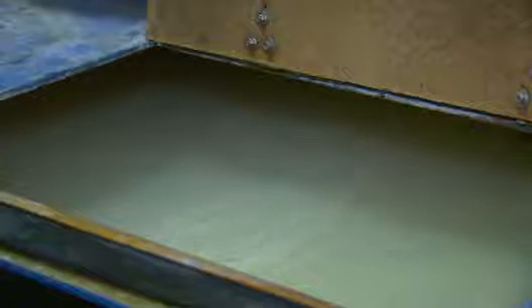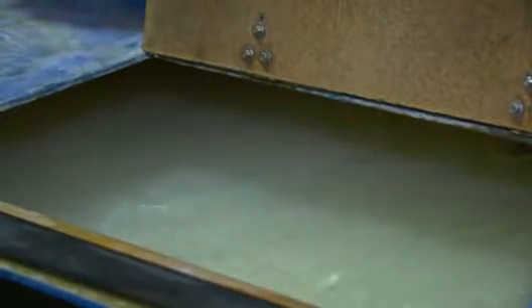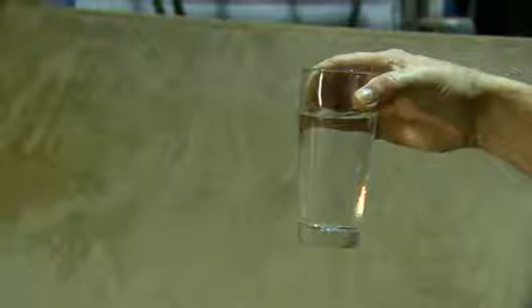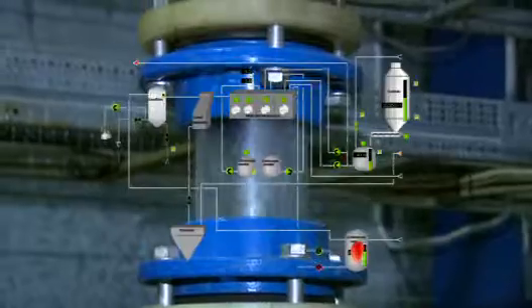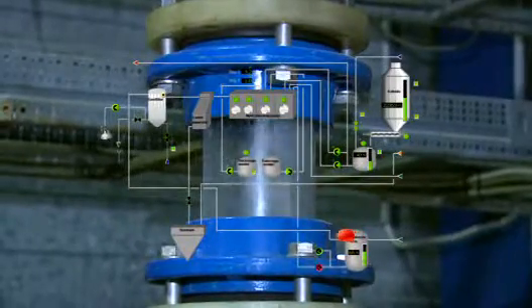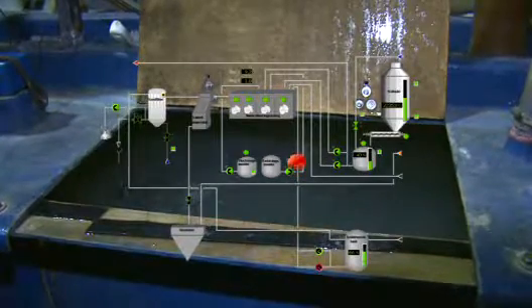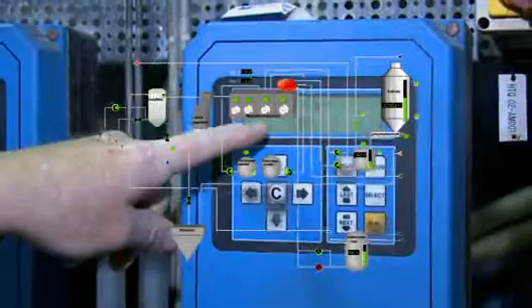It is not enough that the smoke gases are being cleaned efficiently. Also, the water which has been used for the washing out will afterwards be neutralized by adding lime and chemicals in the water cleaning facility at the station before it is directed out to the council sewer system. By this time it is almost as clean as drinking water. To clean the smoke gases, about 1.5 cubic meters of water is being changed every hour. This water is very sour and is therefore channeled to a neutralizing facility.